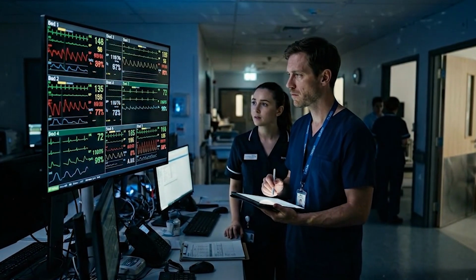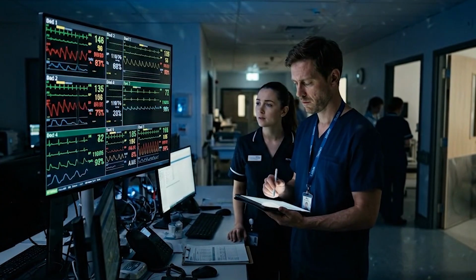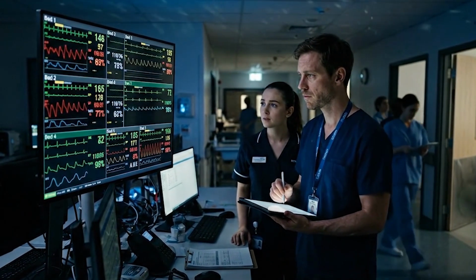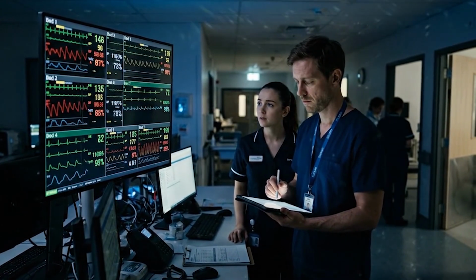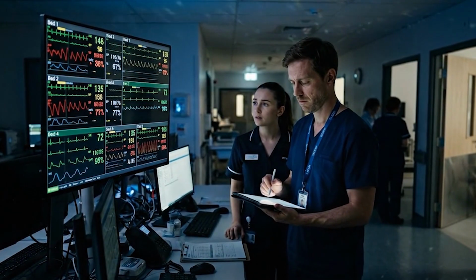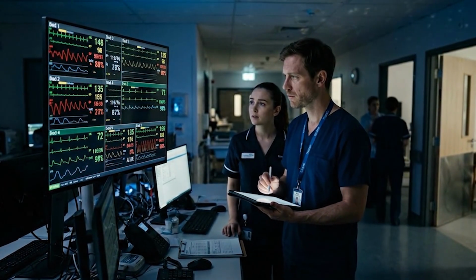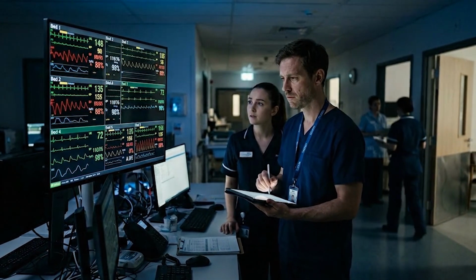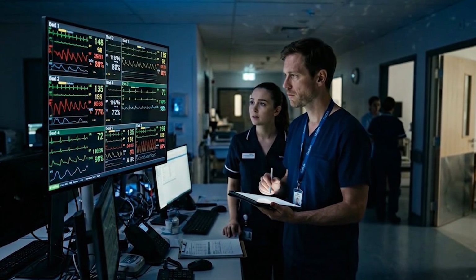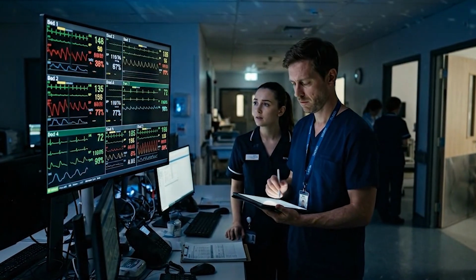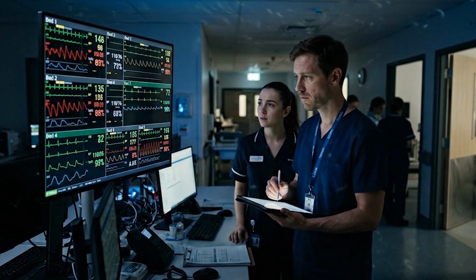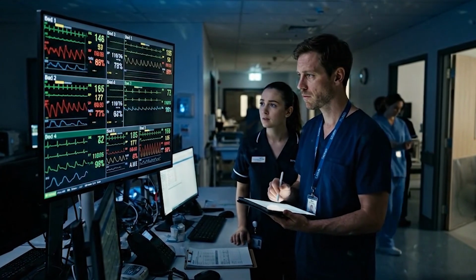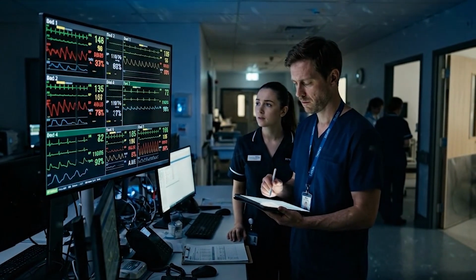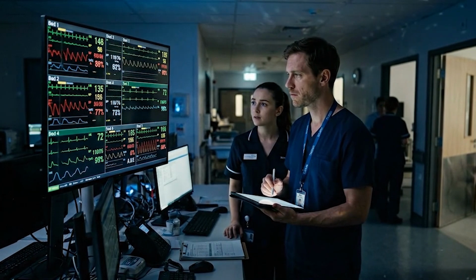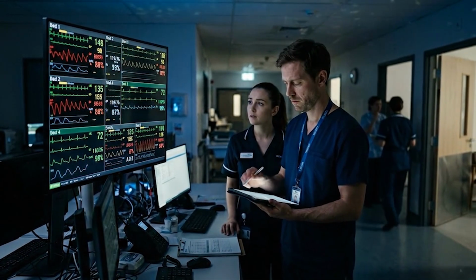And the responses ranged from Tom saying he was waiting on Philips to the nursing staff saying they'd stopped paying attention to it because the data wasn't attached to a real patient chart and therefore didn't affect clinical care. The phantom vitals existed in a system limbo, visible on the monitors, present on the central display, but linked to no patient record, no medical record number, no name.